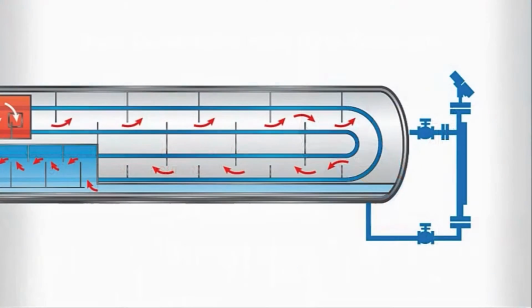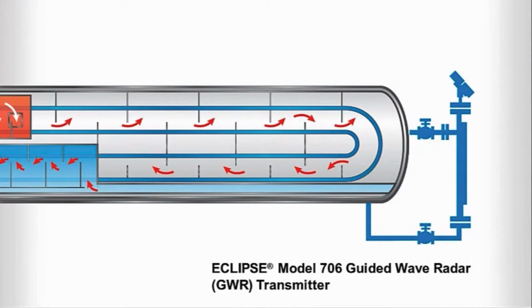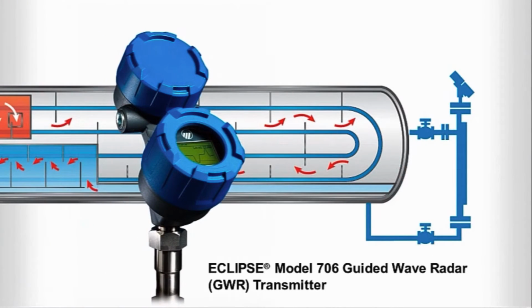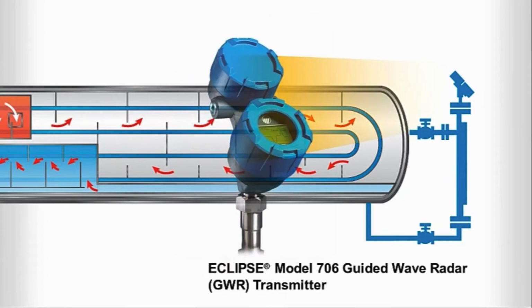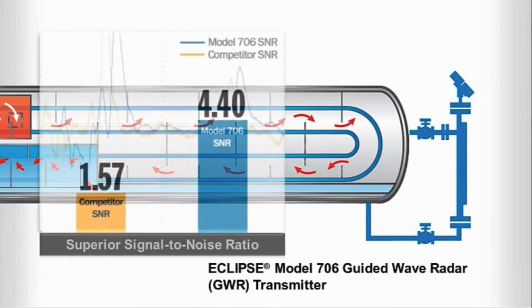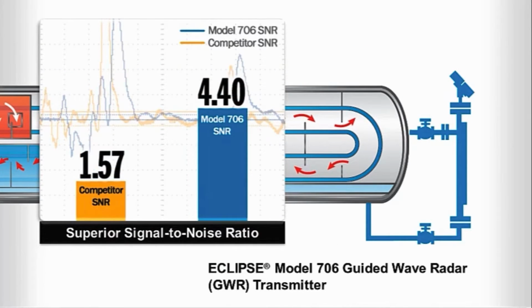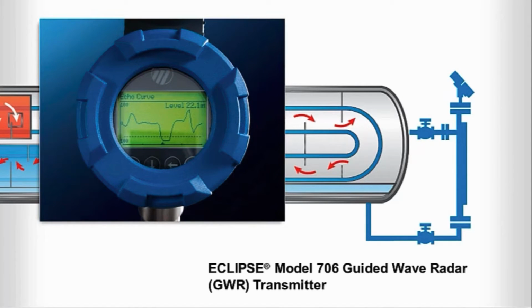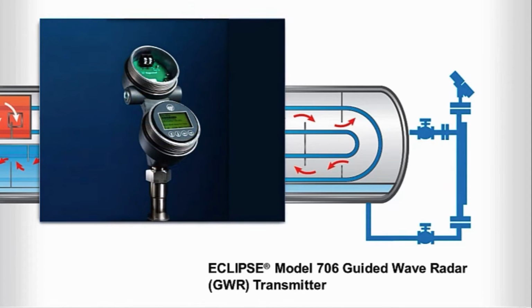Magnetrol's new Eclipse Model 706 provides enhanced guided wave radar performance, virtually unaffected by process variations. The Eclipse Model 706 gives you a superior degree of accurate and reliable continuous level measurement without the need for calibration or gravity corrections. By combining superior signal performance and advanced diagnostics, the Eclipse Model 706 delivers premier level control for feedwater heaters, as well as a broad range of challenging applications such as condenser hot wells, deaerators, and cooling tower basins.